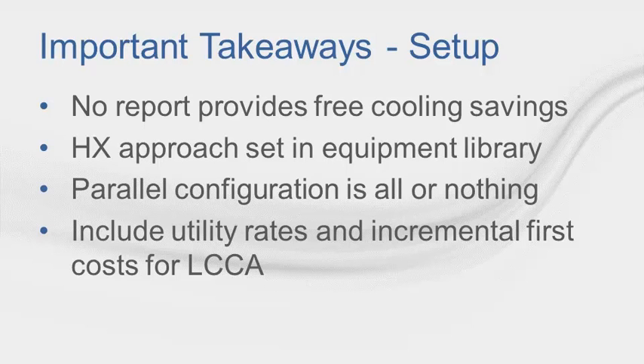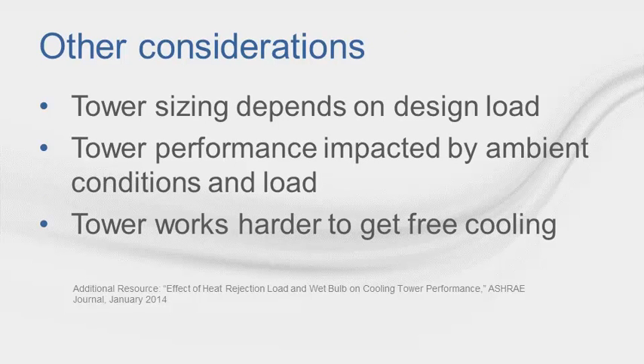We're ready to calculate. Setting up the free cooling is easy, but remember, there must be a base alternative created in order to determine savings due to free cooling. The default heat exchanger approach can be modified in the equipment library and defaults to 3°F. When a heat exchanger is configured in parallel, it operates only when it can meet the entire cooling load in any given hour. If a lifecycle cost analysis is to be performed, the proper costs and utility rates must be entered for the project alternatives.